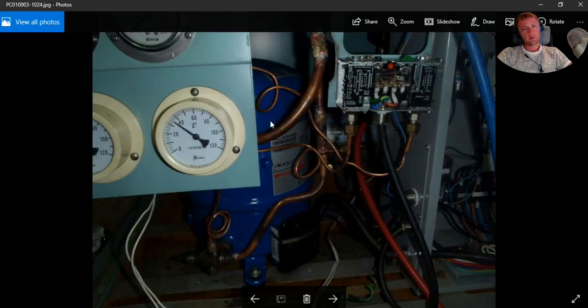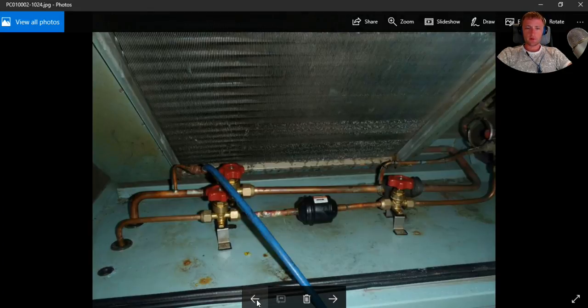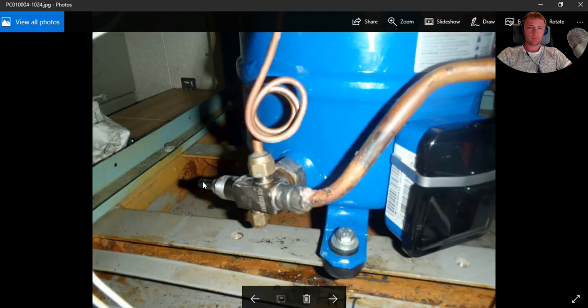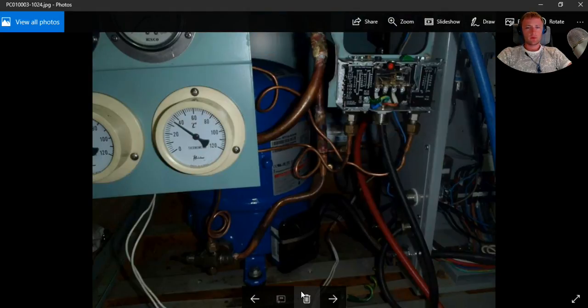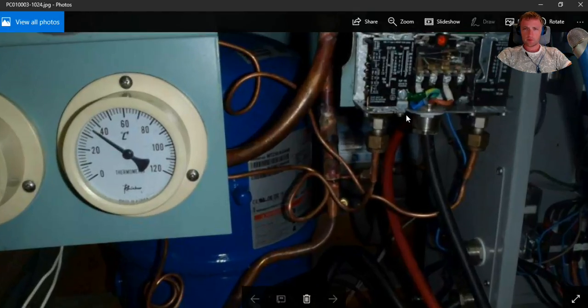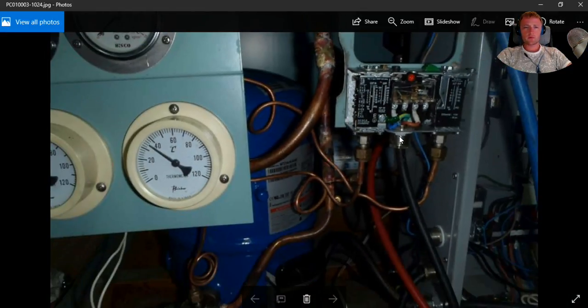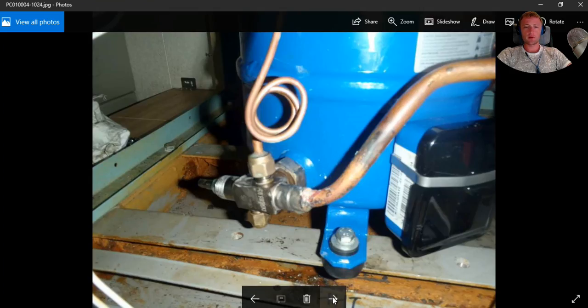We made welding here. This is the connection, and from here you can isolate your compressor. Here is the test for vacuum, here is a connection for the vacuum. And let's go here, you can see you can close with this connection and isolate. From here it's going to the pressure. We have some points for pressure cut off and start, and some of the pipes go there for indication of the vacuum and the discharge pressure.